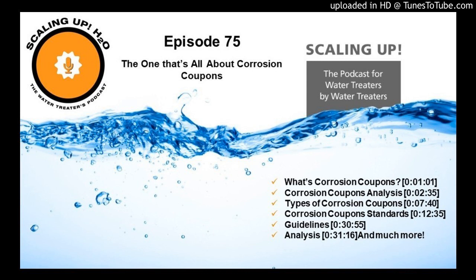So you want to make sure that the systems are running, because it is impossible to treat a system that is not. But you're looking at all these things, and now you're going to apply the data that you got from that corrosion coupon to your system, making a change, and then in your next exposure rate on your next series of corrosion coupons, you will be able to see what type of an effect you had on that system. Again, I look at corrosion coupons as a very inexpensive, proactive approach for us to get more data about the system that we are treating.